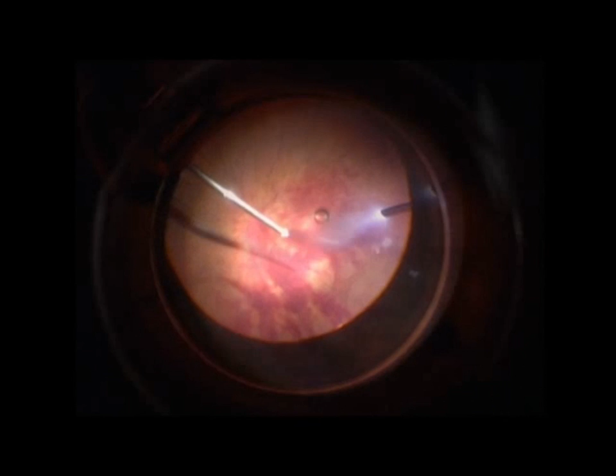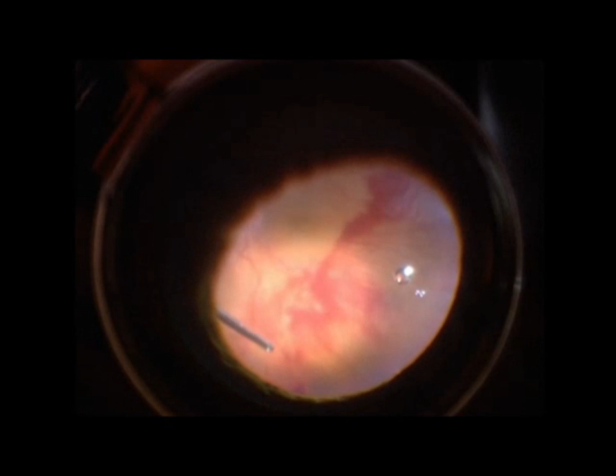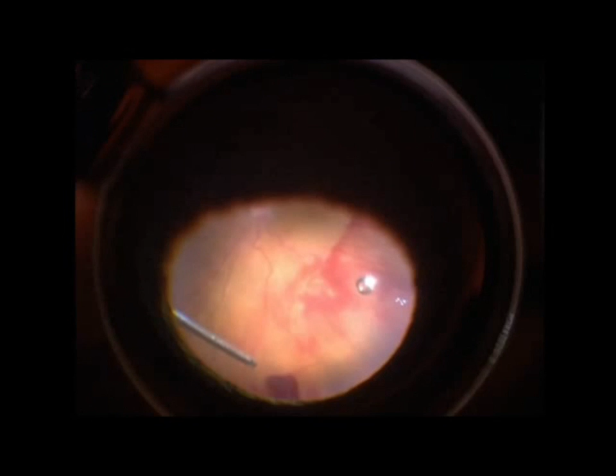We can see the improved flow. It's 40% greater at 3,000 cuts per minute, 28% greater at 4,000 cuts per minute. And for a core vitrectomy I pretty much routinely keep the cuts per minute at 4,000. The only thing that changes when I push down my foot pedal is my aspiration, running anywhere from 50 millimeters of mercury at treadle start to 500 millimeters of mercury at full treadle.